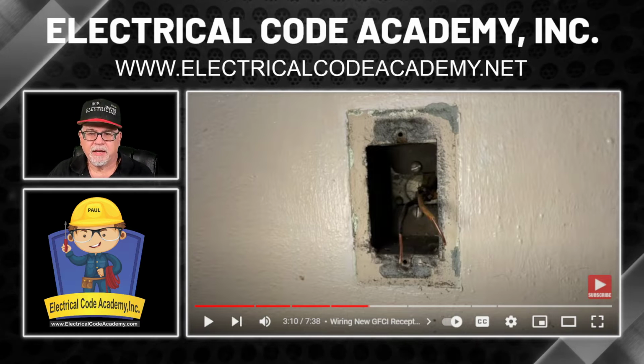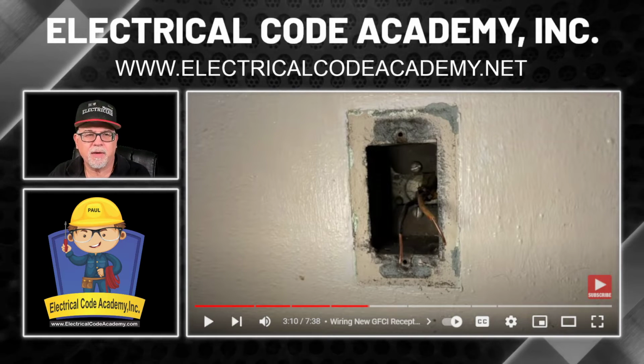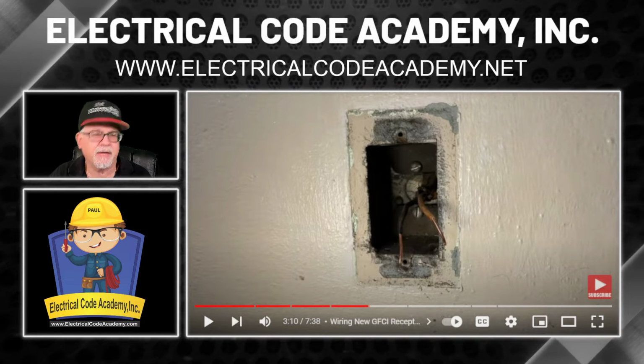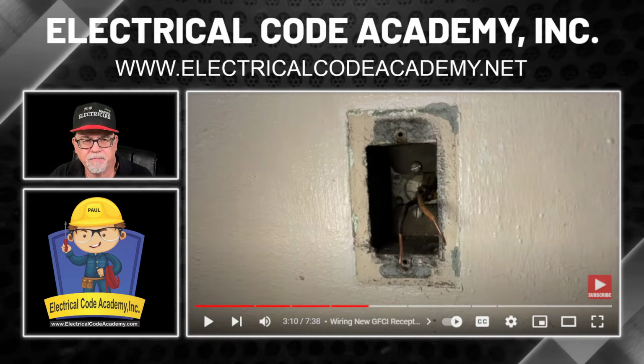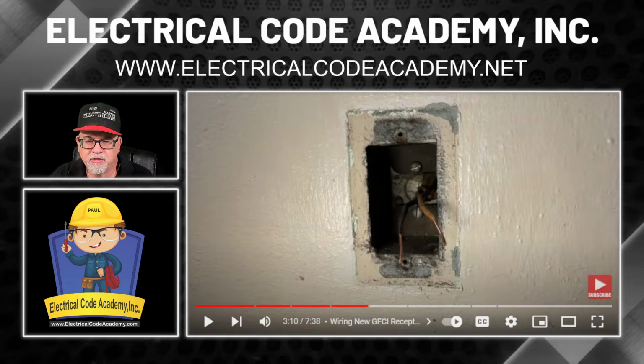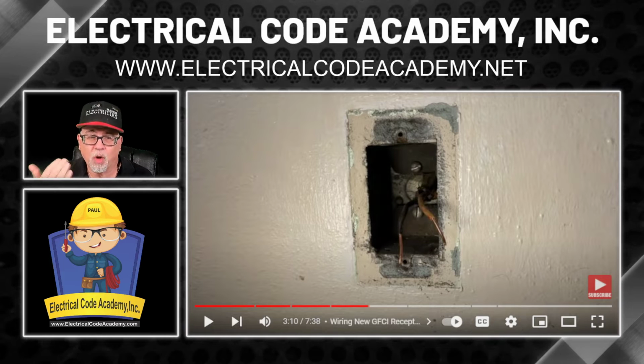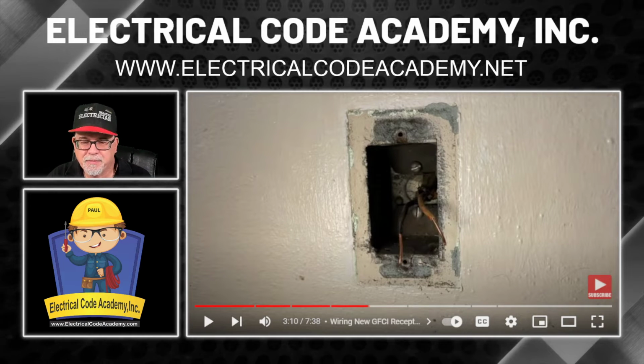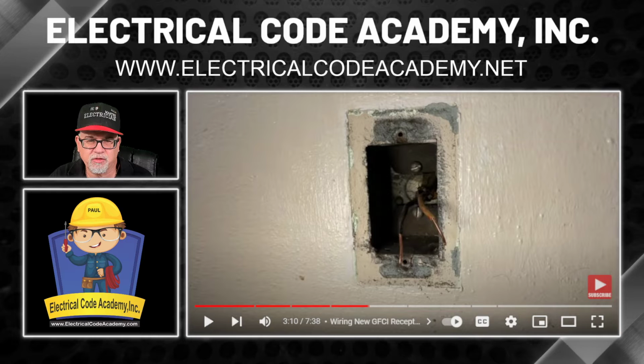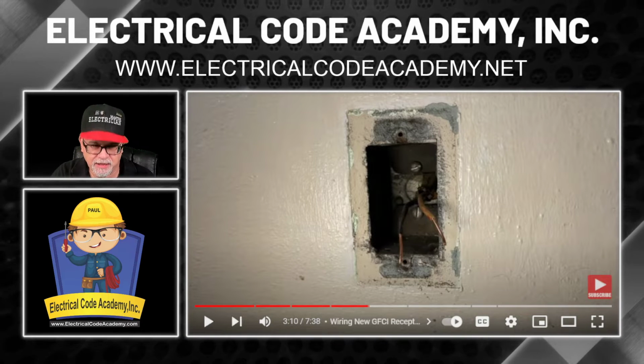Okay, only a couple things I want to add here. Obviously, y'all know he meant strip insulation and not strip off copper. He was exposing the copper. Couple things. The National Electrical Code requires, and this is older, so it probably predates that, but it requires us to have at least 6 inches of free conductor as it enters from the cable into this box.